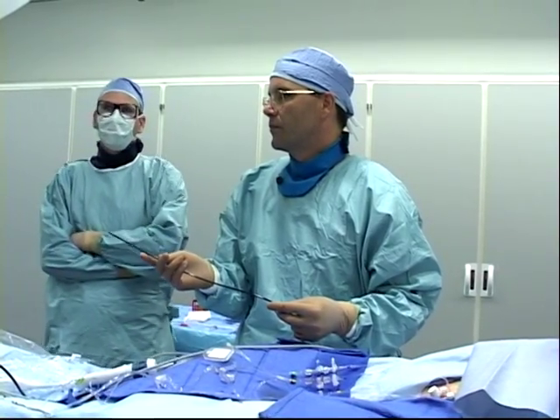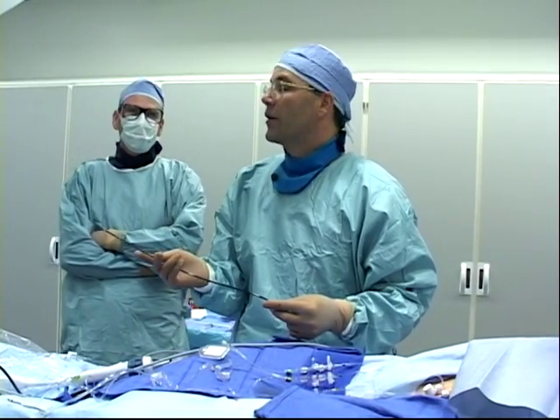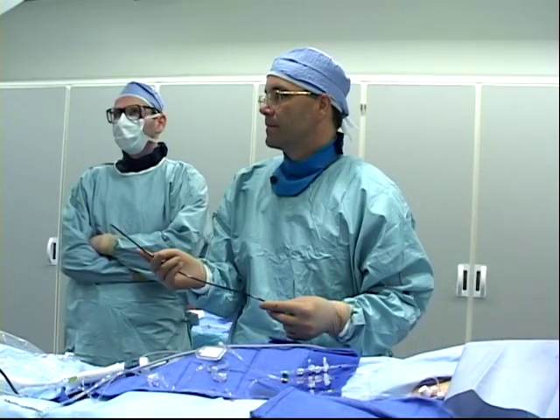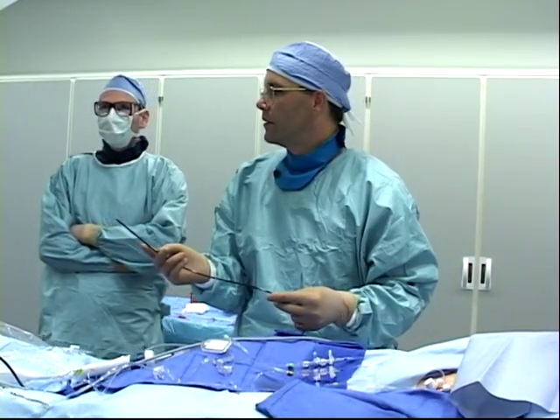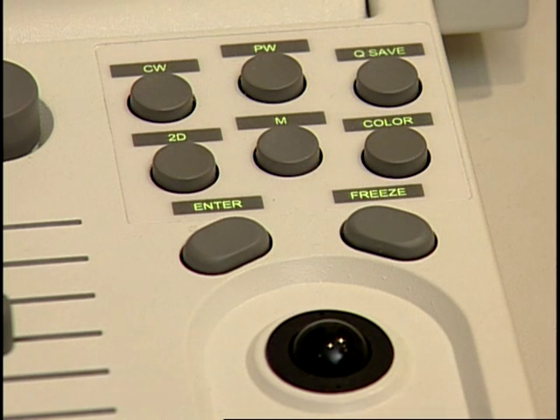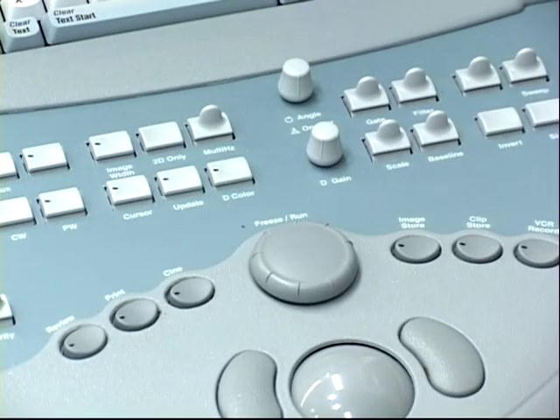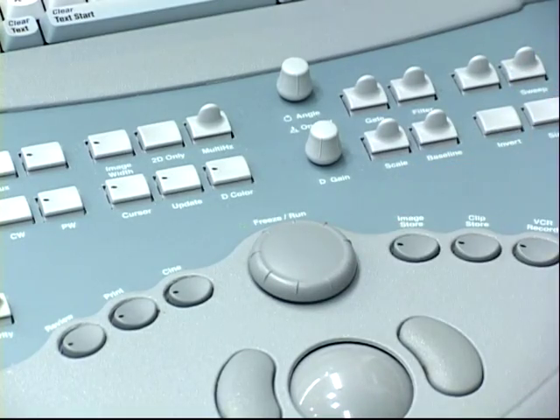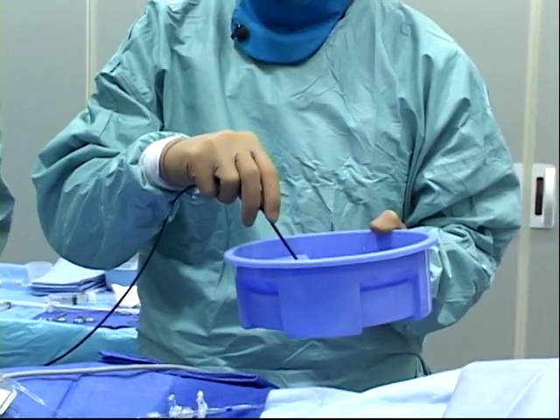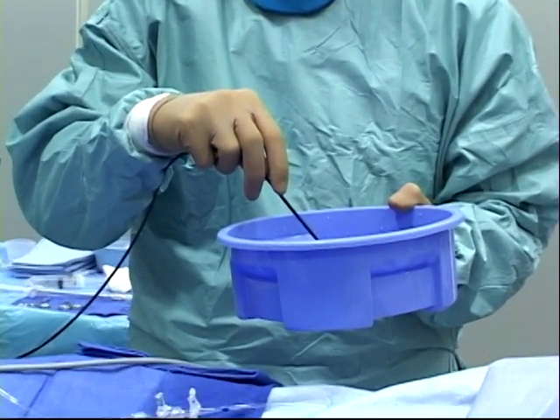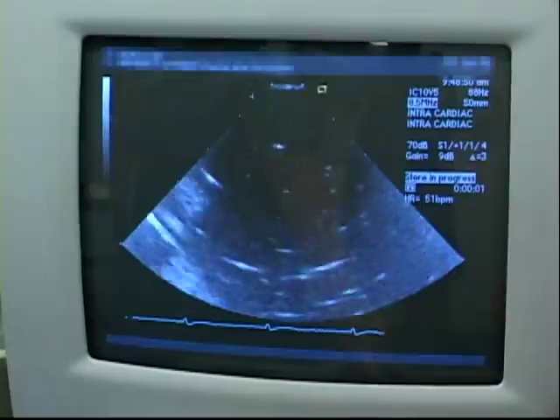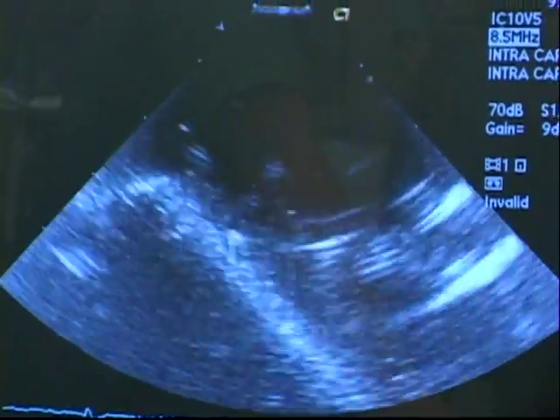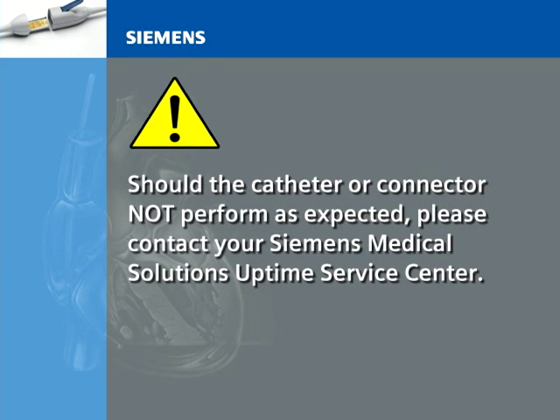With the sterile sheath now in place and the SwiftLink connector connected to the ultrasound system and to the catheter, verify that the catheter is imaging before inserting it into the patient. After the ultrasound system is turned on, unfreeze the image on the screen by pressing the Freeze Run button. Using sterile technique, place the tip of the catheter in a container of sterile saline and use the tip of the catheter to move the saline solution around in the bowl. You should be able to detect movement on the screen while the saline solution is moving. Should the catheter or SwiftLink connector not perform as expected during the pre-procedure inspection process, please contact your Siemens Medical Solutions Uptime Service Center.